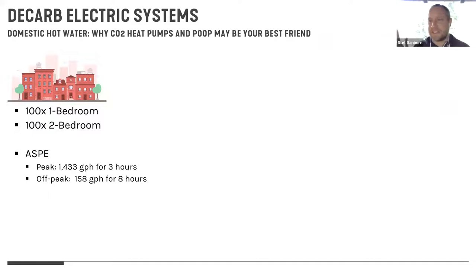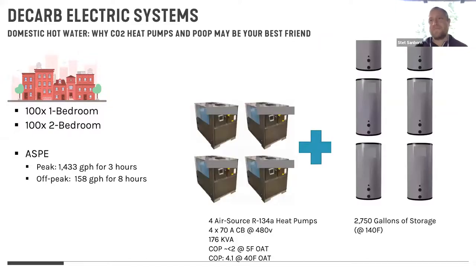Now, there are going to be some regional differences for sure. So I wanted to run one. This is assuming air source heat pumps, good size central air source heat pumps paired with storage for this fake 200 unit building. In order to hit the capacity that I need for this particular project, I would need four of the biggest air source heat pumps that this company makes.